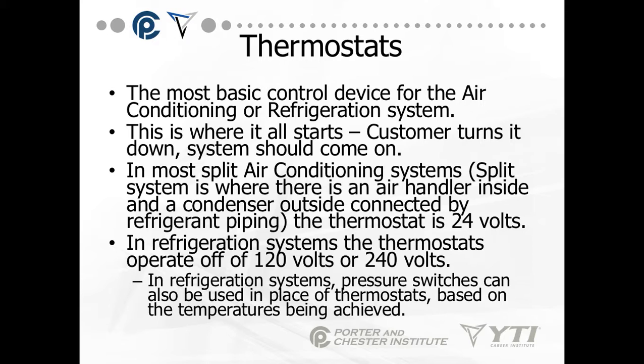There's a difference between the thermostats found in refrigeration and those found in air conditioning. In most air conditioning systems, our thermostats are 24 volts. In refrigeration systems, the thermostats actually are line voltage and directly control, in most cases, the compressor and the condenser fan as well as some other controls. In refrigeration systems, you have to remember that they operate on 120 volts or sometimes 240 volts.